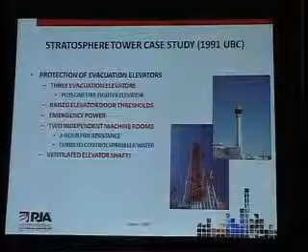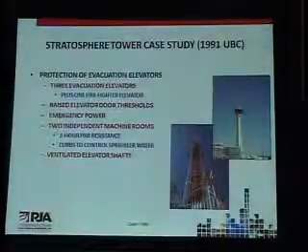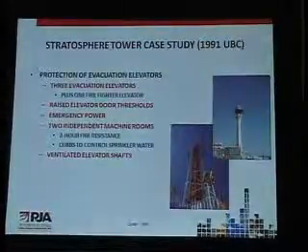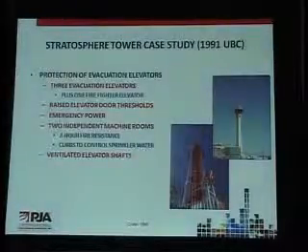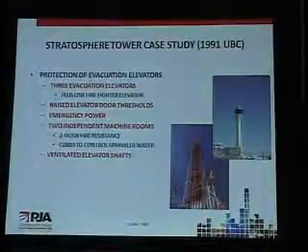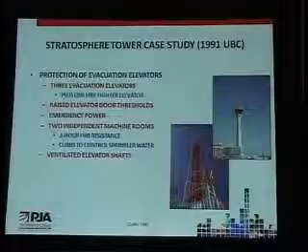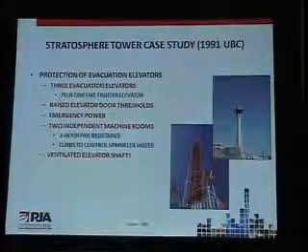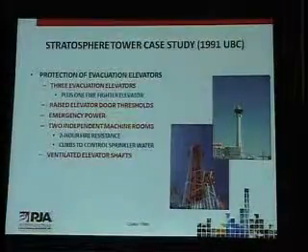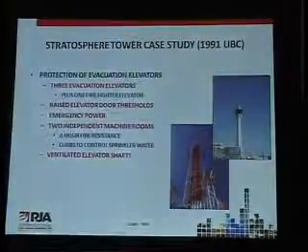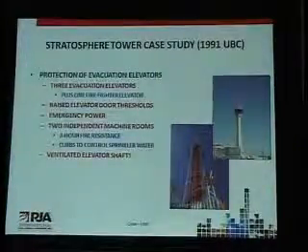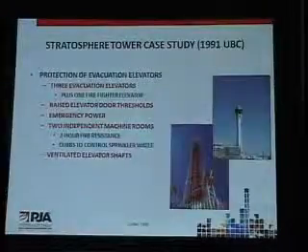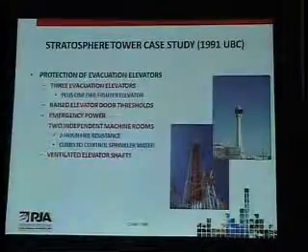So this is a rather unique case study because it does rely on elevators to evacuate the building. There are 3 evacuation elevators plus 1 firefighter's elevator. Some of the strategy that they've employed, prior to even the 2009 edition of these requirements coming on board, 18 years before, was raised elevator door thresholds and emergency power.